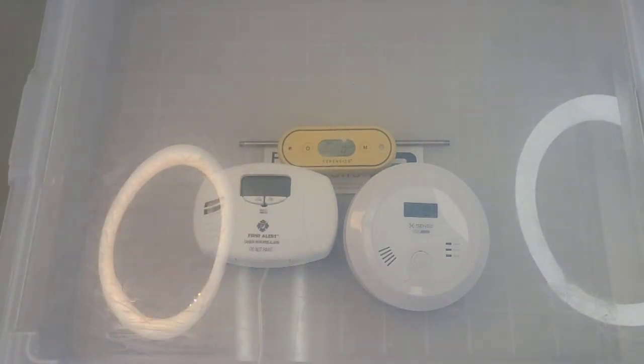We're going to turn on the gas, give it a squirt, and the point here is to see the reaction of carbon monoxide on various detectors — to see how they alarm, the alarm protocol, the speed, and also to see if things are in agreement in terms of carbon monoxide concentrations.